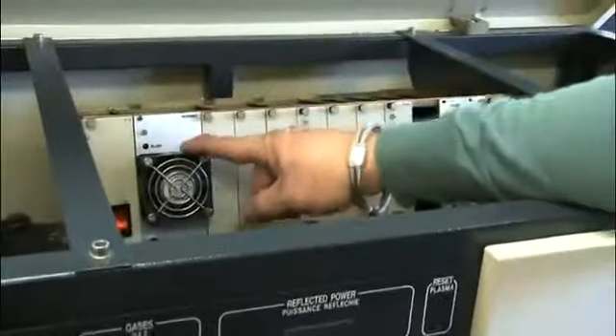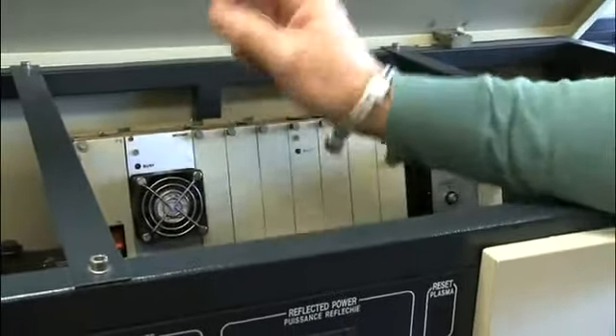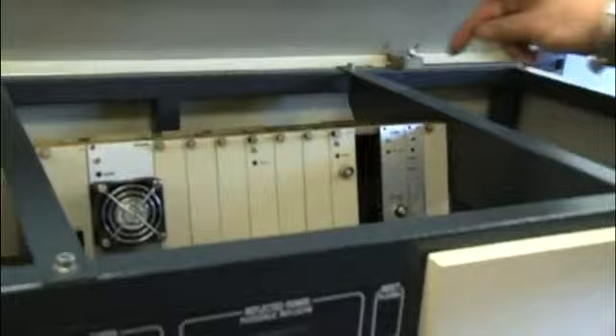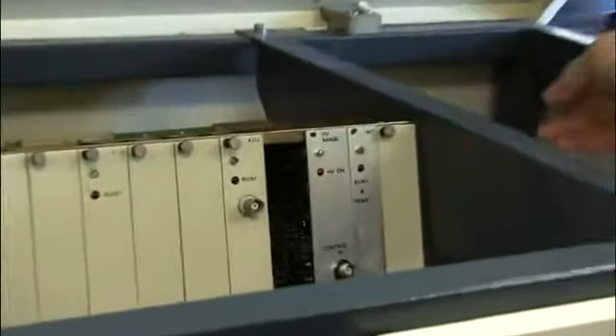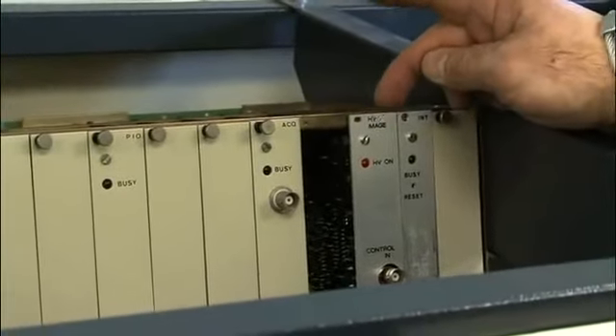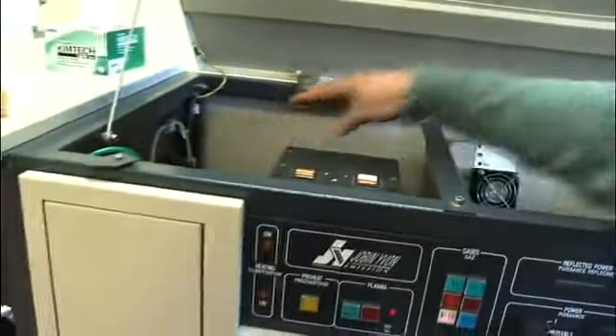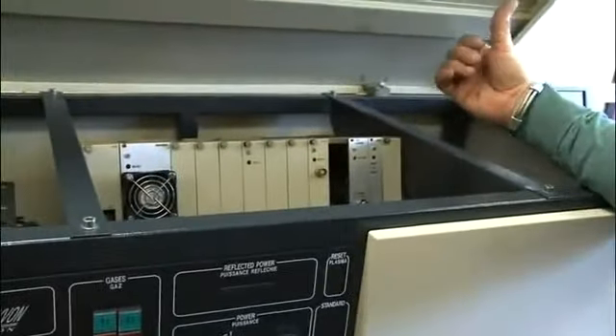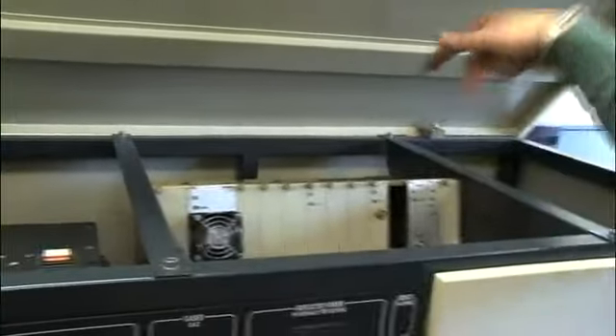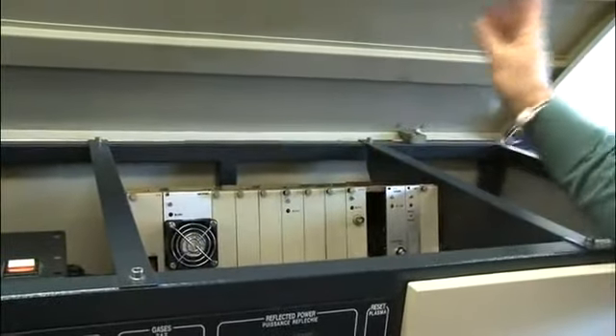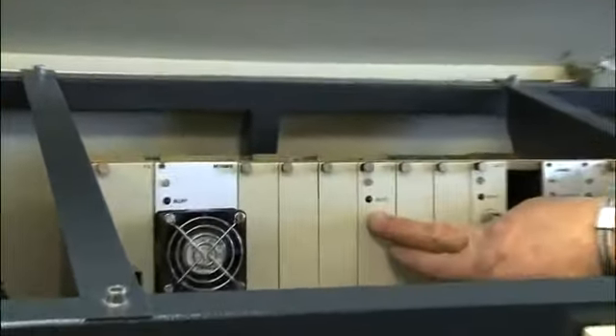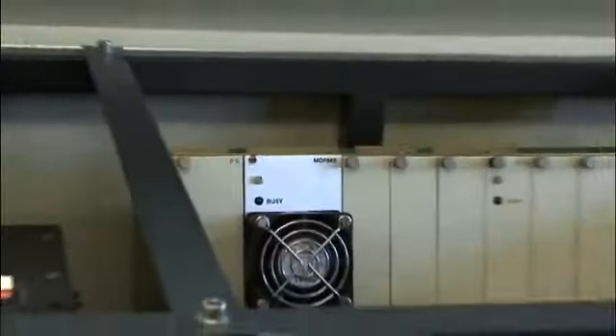Some of the boards here, I'll tell you what they do. This is a power supply for the boards that are plugged in here. This board, the MDRMS, its job is to move the grating. Interface board is what communicates to the computer. The high voltage is what adjusts the high voltage on the photomultiplier tube, and that's adjusted automatically with the software. The acquisition board takes the electrical signal from the photomultiplier tube and converts it to a frequency. That goes out to the computer also. This PIO board just controls your slits.